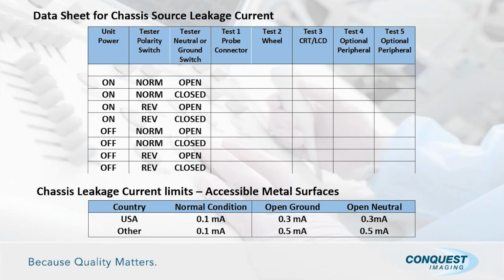Now here's the data sheet that you'd need to fill out when you're looking at chassis leakage, and it tells you the different conditions. You have to have the unit power on and off, you have to have the polarity switch on normal and reverse, and you have to have your neutral open and closed. So you need to test to all these conditions.